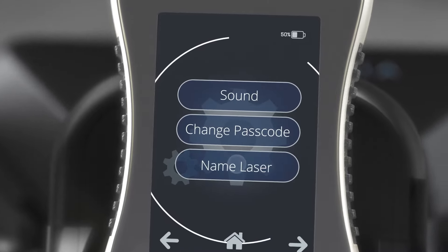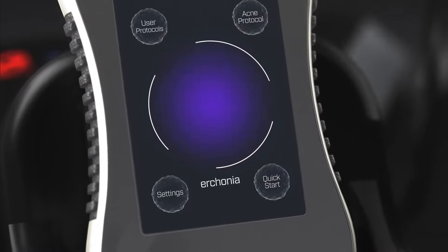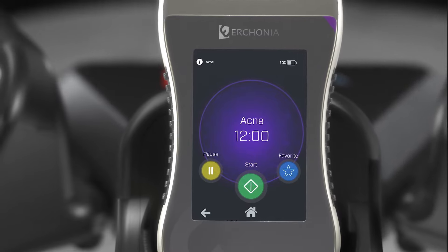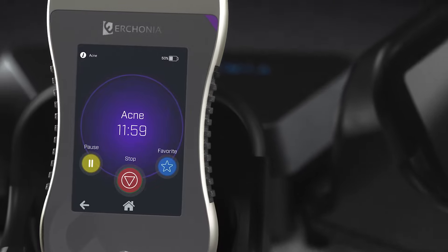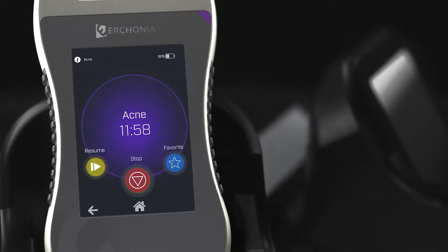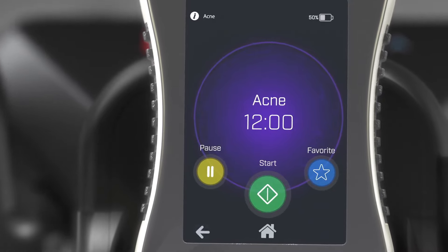You can also personalize your laser by naming it. Input the desired name, and the home screen will display the new name. Next, let's look at the Acne Protocol, which is a preset protocol specific to the EVRL device, which is FDA cleared to treat acne. To start, simply select Start. Pause will halt the laser without resetting the clock until Resume is pressed, then the clock will continue counting down. The Stop button will stop the laser and reset the clock. Pressing Back will take you back to the home screen.